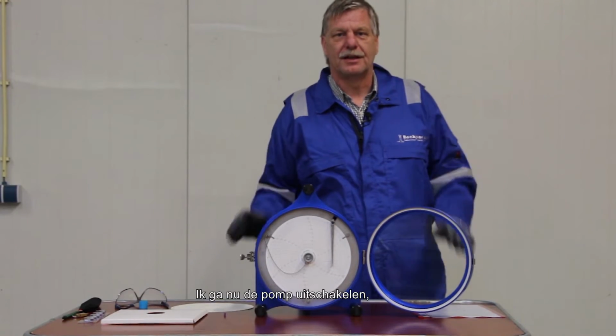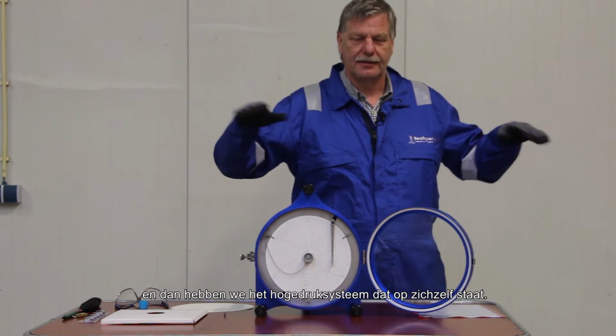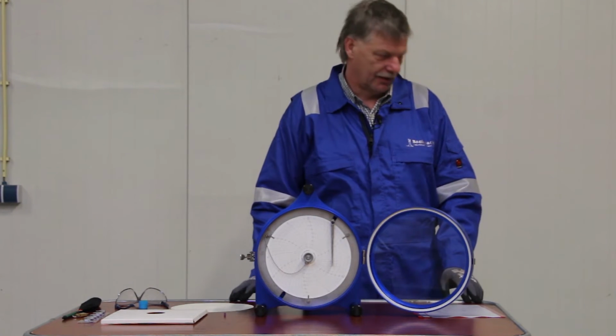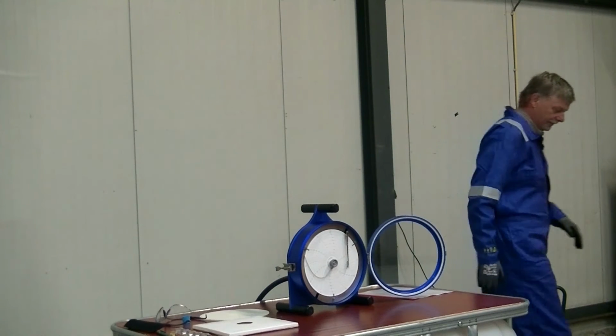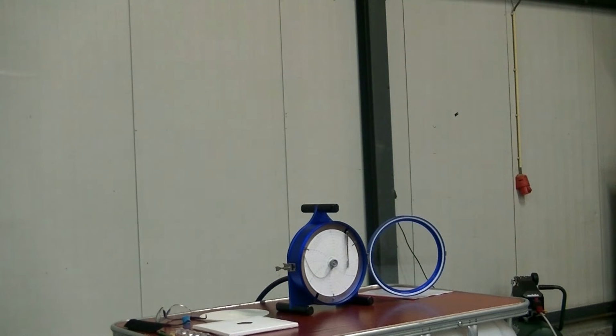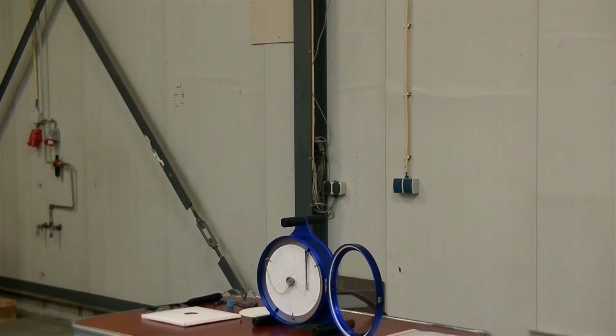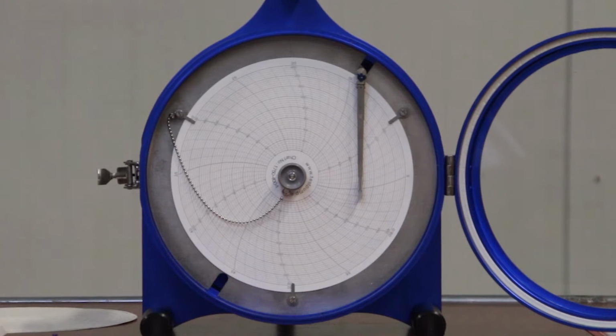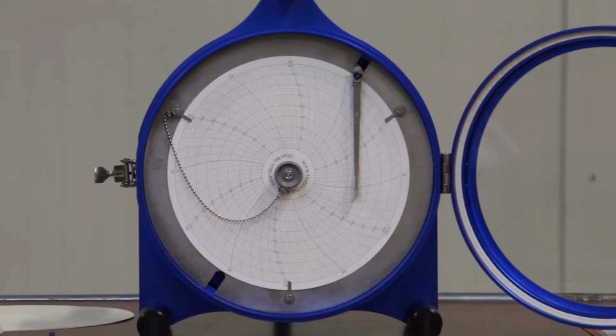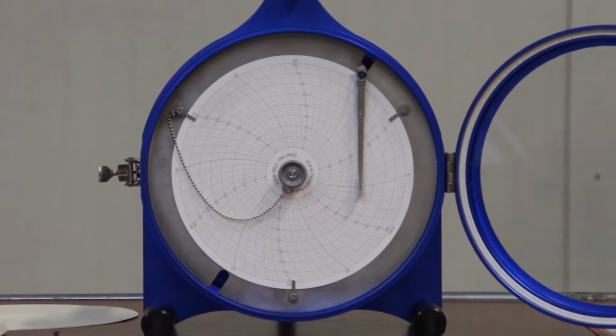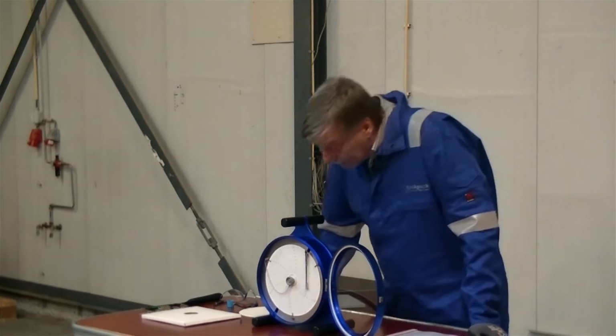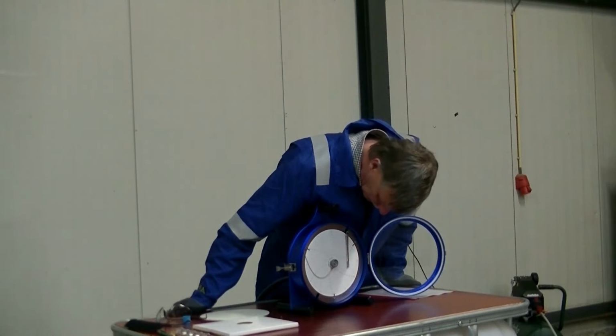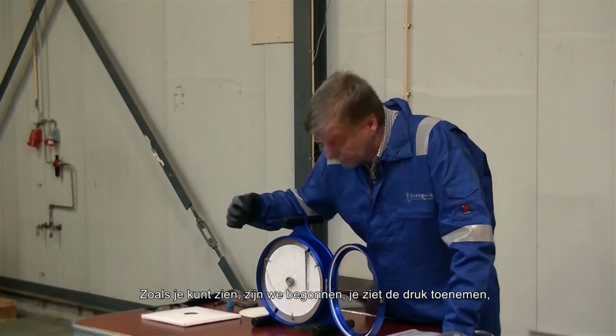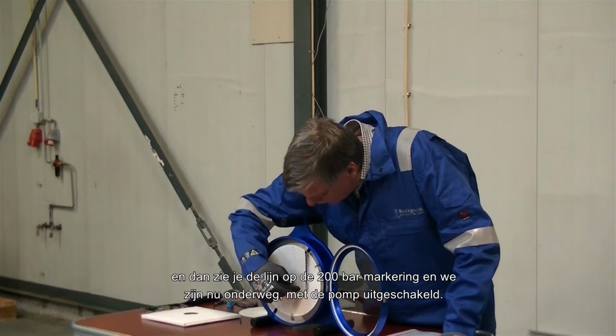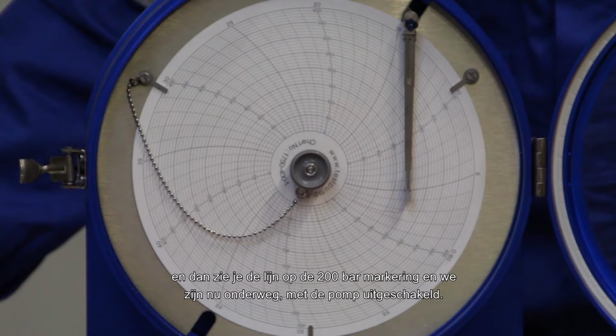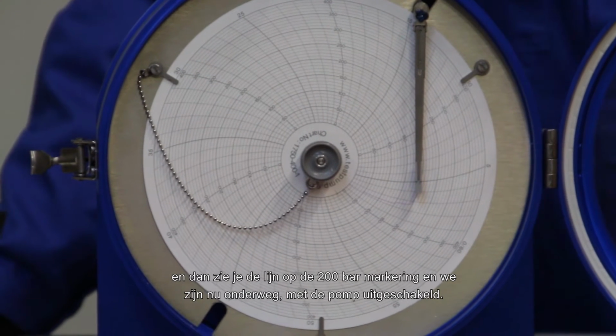Let me take the pump out of the equation, and we've then got the high pressure system standing on its own. As you can see, you see the pressure build up, and then you see the line over the 200 bar mark. And we're en route now, with the pump taken off.